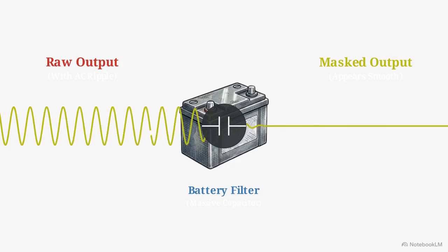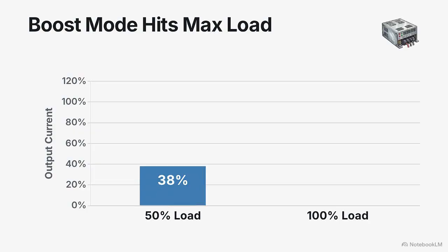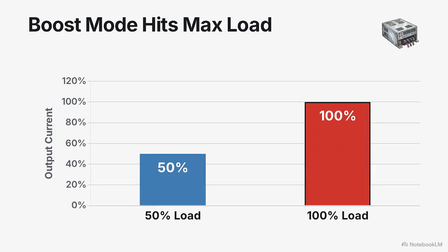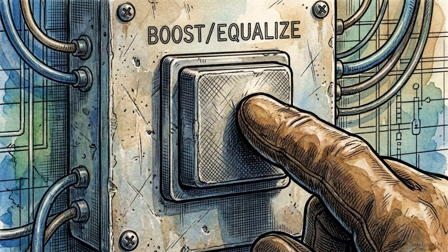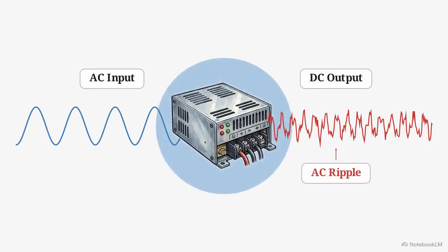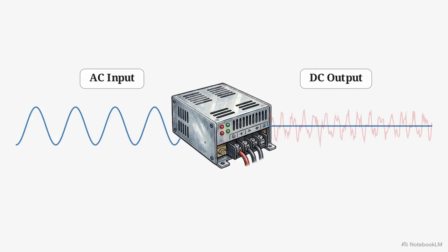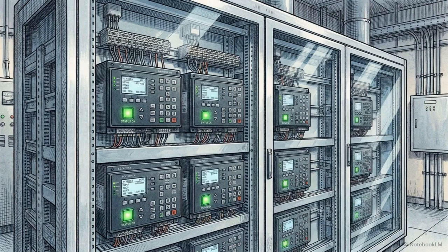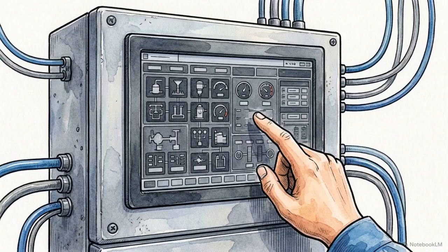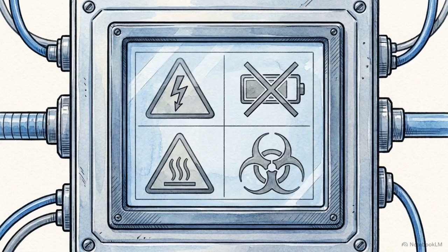The 50 and 100% load steps are then repeated, but this time with the charger forced into boost or equalize mode. Verifying this efficiency and strictly limiting any alternating current ripple on the DC line is vital to protect the substation's delicate, microprocessor-based protection relays from long-term degradation. Beyond power conversion, we have to verify the charger's logic controls. This means checking the human-machine interface to ensure its protective alarms trigger correctly.